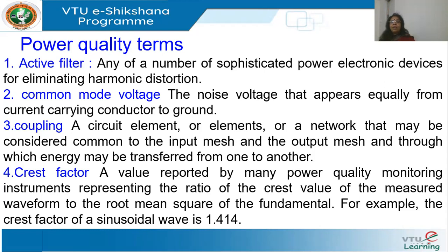Passive filters have bulky inductors and capacitors, and they cannot do multiple things simultaneously — for example, they cannot compensate for power factor, balance, and harmonics all at once. In the past decade, a lot of work has gone into designing and manufacturing active filters. Active filters use power electronic devices to mitigate harmonic distortion. Power electronic devices are both the source of the problem and also the solution — harmonics arise mainly from power electronic devices in modern industry, and using them, we provide a solution.